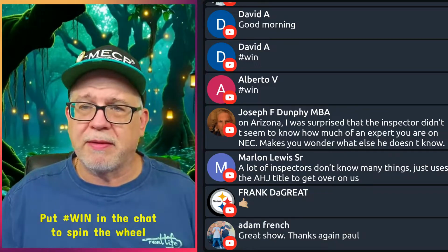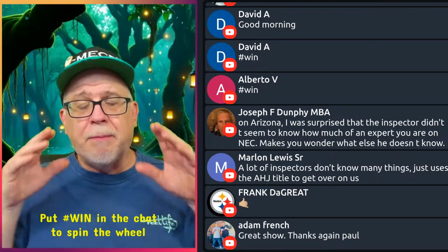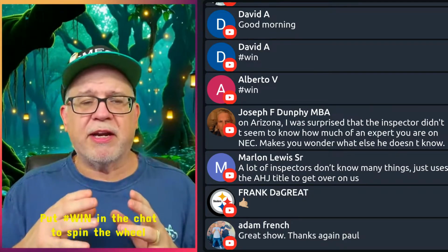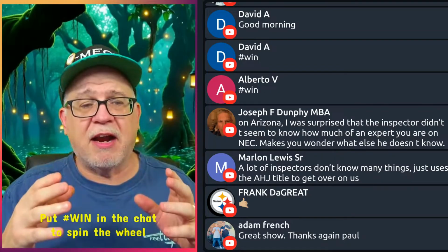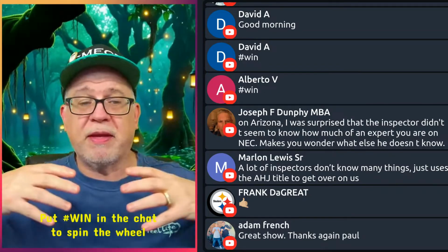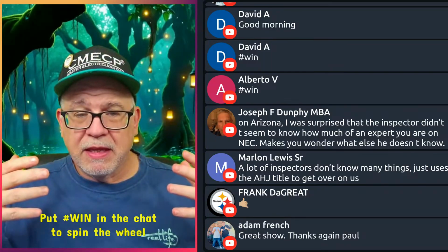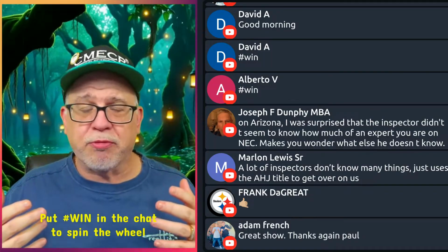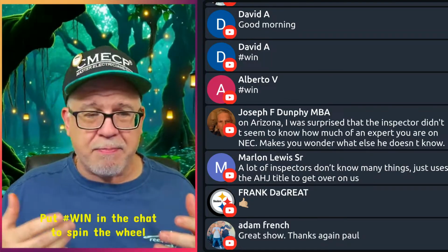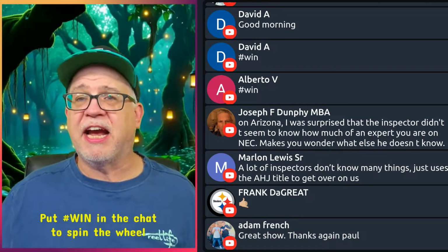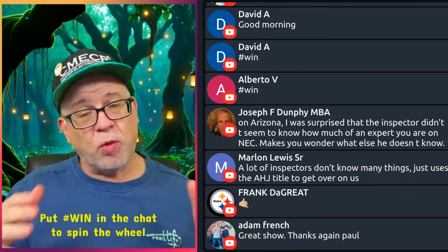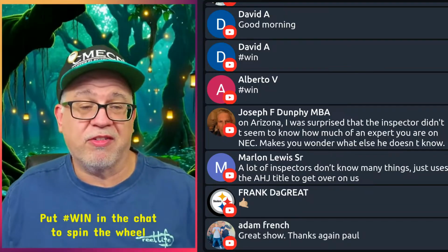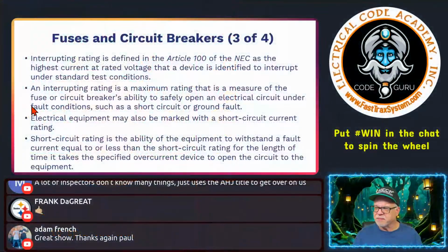You're going to have to do it. But again, my point was, you take a breaker that's rated for normal standard testing, you put it in an environment where the ambient temperature is going to be above that, and yes, you're going to get premature tripping. Things are going to happen, and you're going to say, well, this is a defect. It's not a defect. It's the condition of use and where you put it. And again, it is what it is. You get what I'm saying?